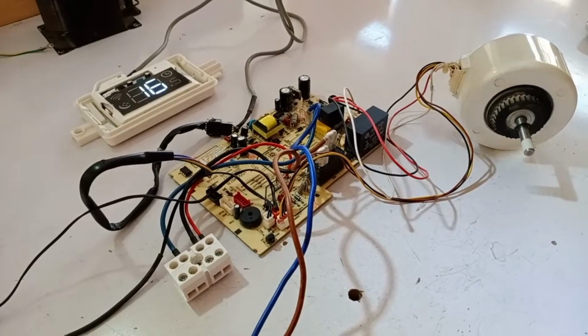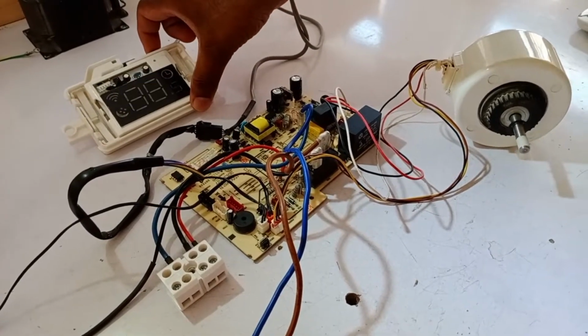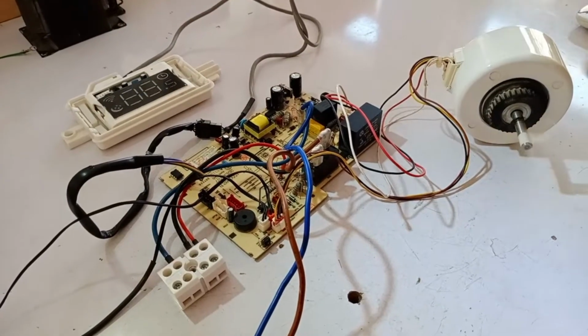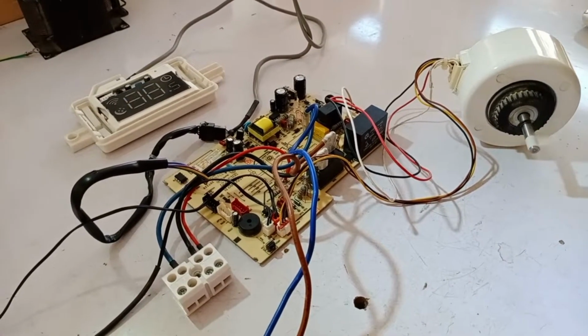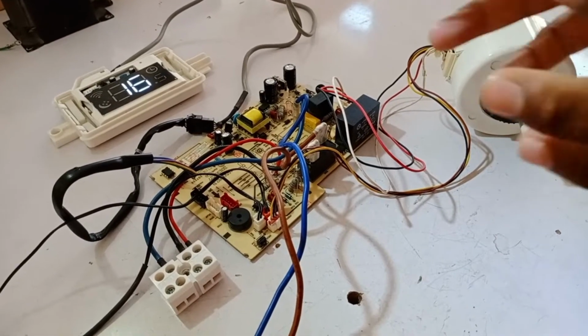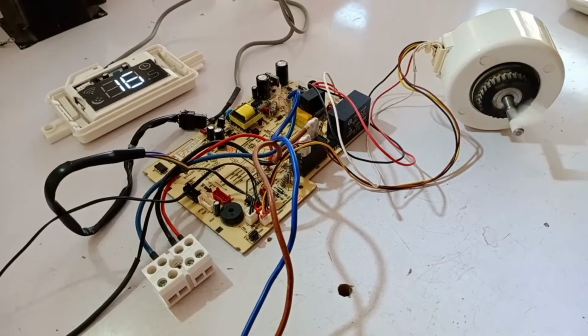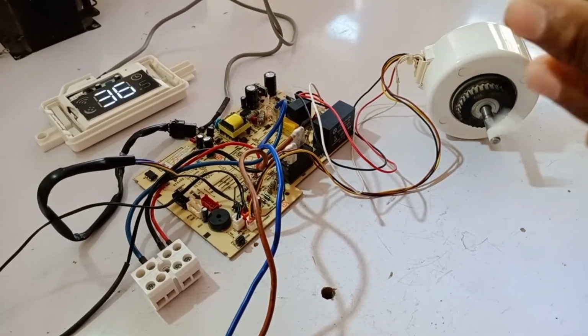Now, you can see that the error code is being displayed on the screen. The error code 36 is showing up. Whenever error 36 appears, the outdoor unit will stop working, but the indoor blower will keep running without producing cooling. Meaning of error 36: serial communication error. This error occurs when communication between the indoor and outdoor units is lost.